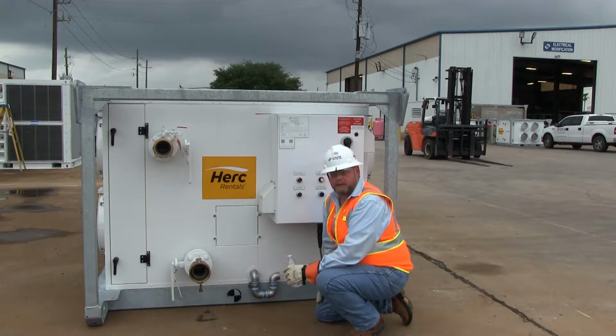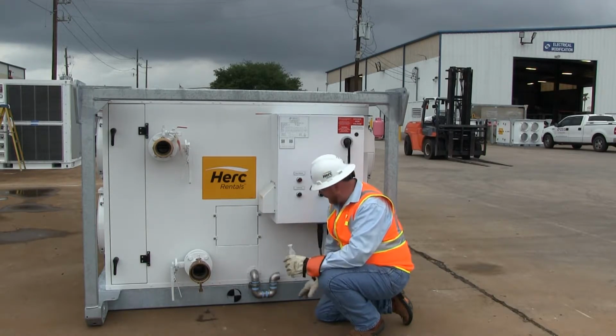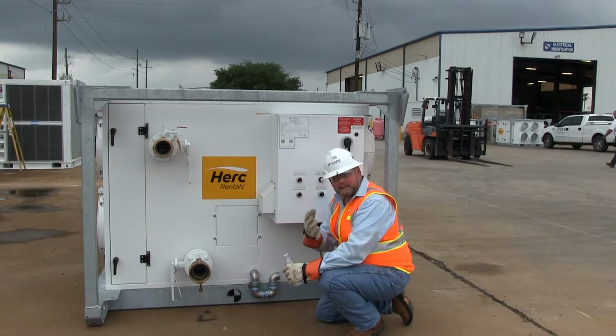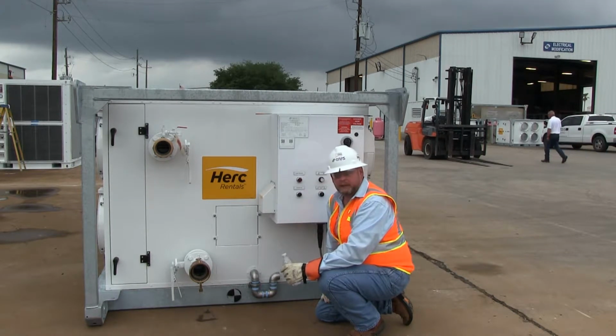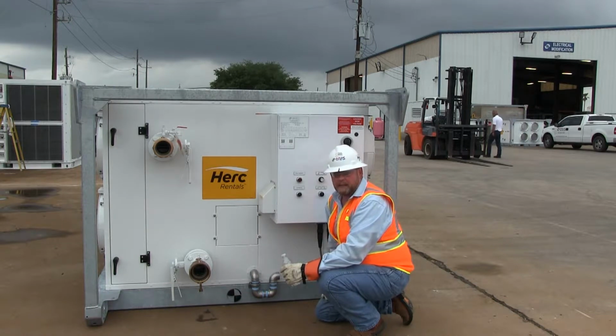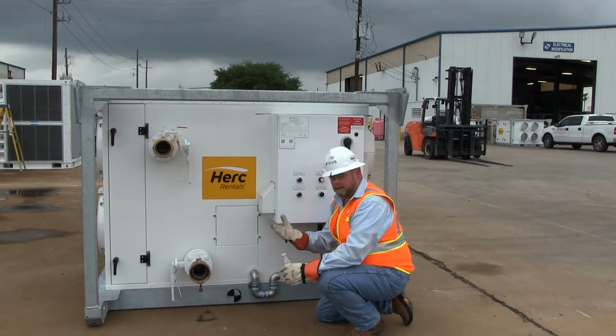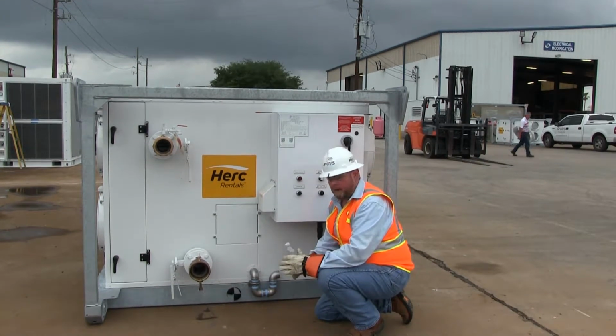The next step in our installation is going to be to prime the condensate trap. Due to the high static nature of these air handling units, they produce a lot of high static pressure and the outside air and the delta T across them. They produce a tremendous amount of water, but you first need to prime the trap.